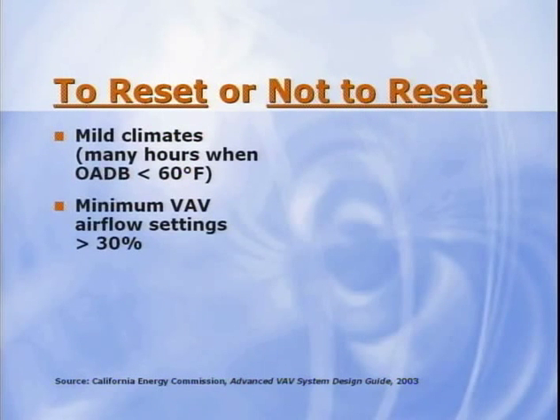Also favoring reset are systems with VAV terminal units that have minimum airflow settings higher than 30% of design airflow. Higher minimum airflow settings increase the likelihood that reheat will be needed to avoid overcooling the zones.